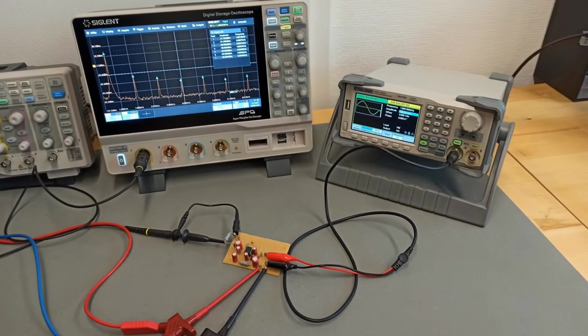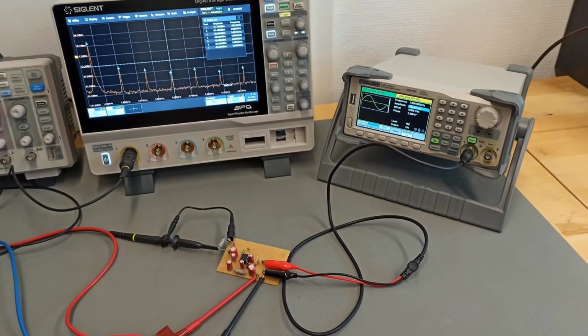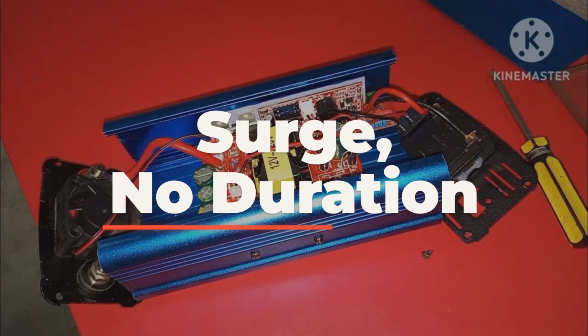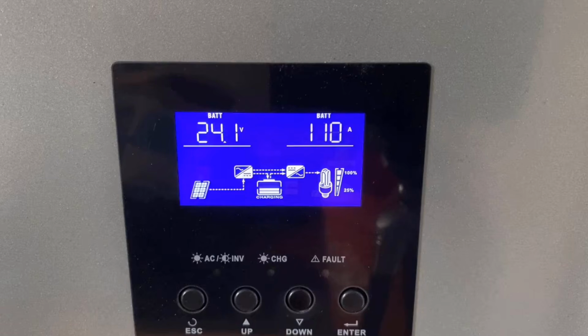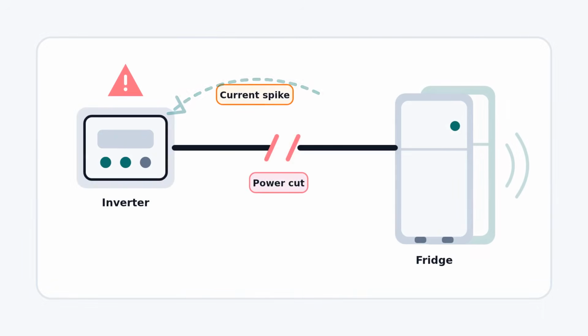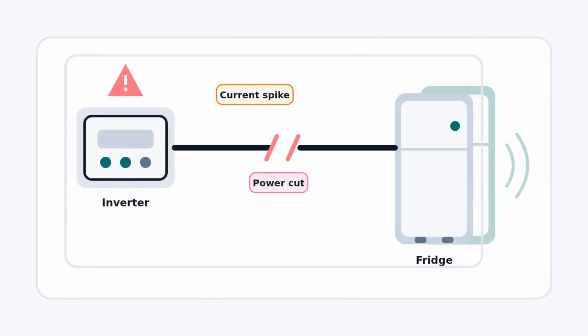A quality inverter handles this with a surge rating and a specified hold time. Cheap inverters list a surge figure but specify no duration. Some cannot sustain even their own peak rating beyond a single cycle before thermal protection trips. The compressor never finishes starting. The inverter cuts out. The fridge shuts down before it ever runs.